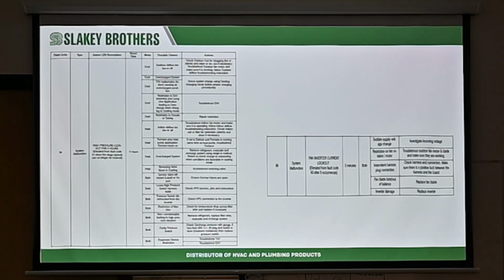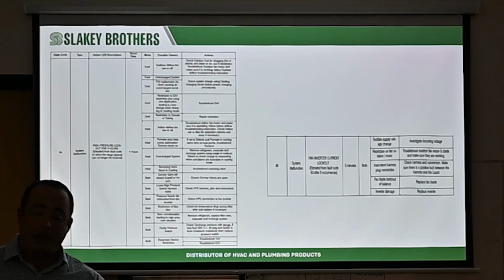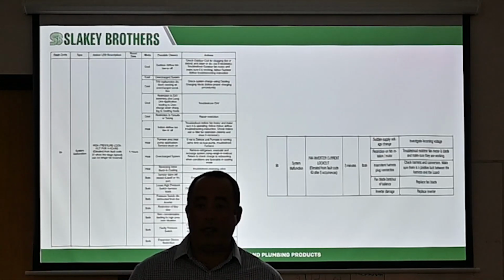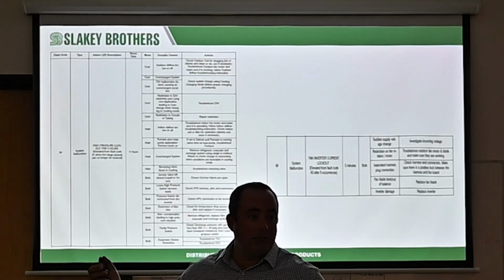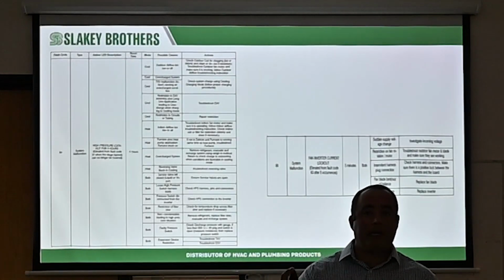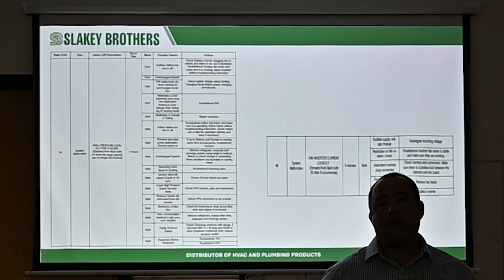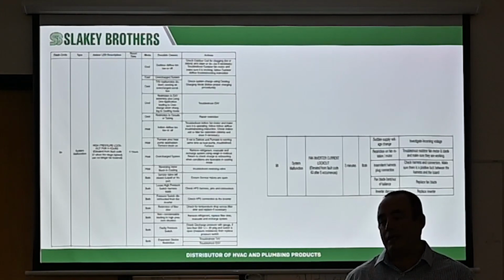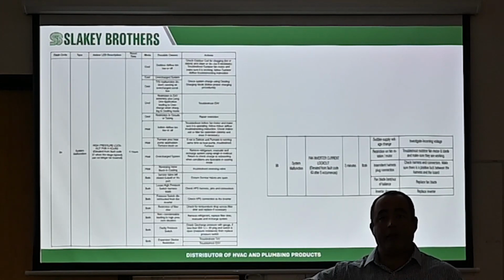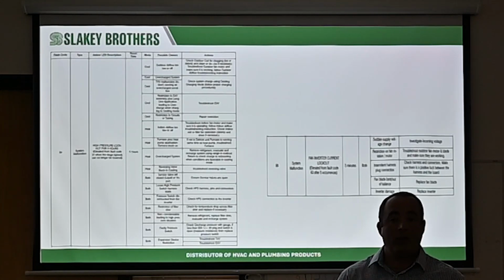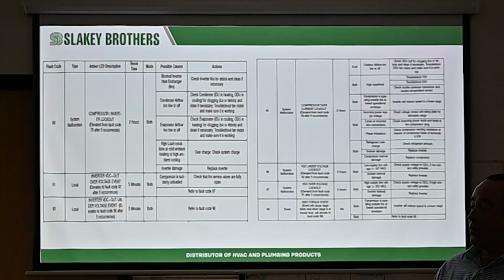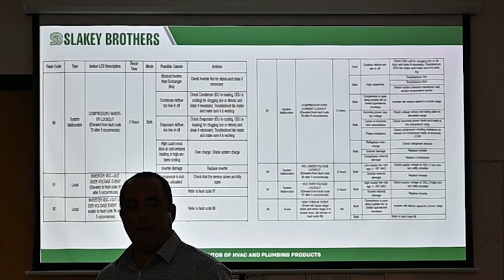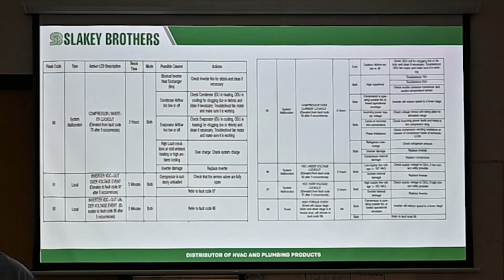Sometimes it's flat out. You can ohm out a compressor and see that the compressor is shorted to ground on these units. Simple diagnostics, right? My compressor is faulty. My condenser fan motor is faulty. It's shorted to ground. Compressor isn't, but my condenser fan motor is. Sometimes those components can knock out these boards, and we find that both in the Evolution variable speed stuff or even in ductless. Okay? But that's why, honestly, we can spend 8-10 hours just trying to go step by step, every single little thing.